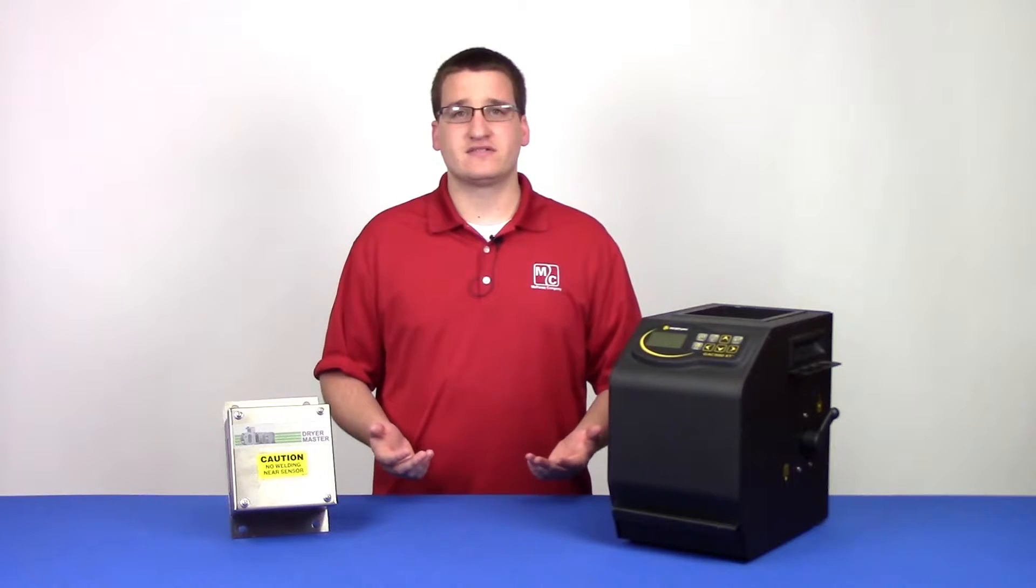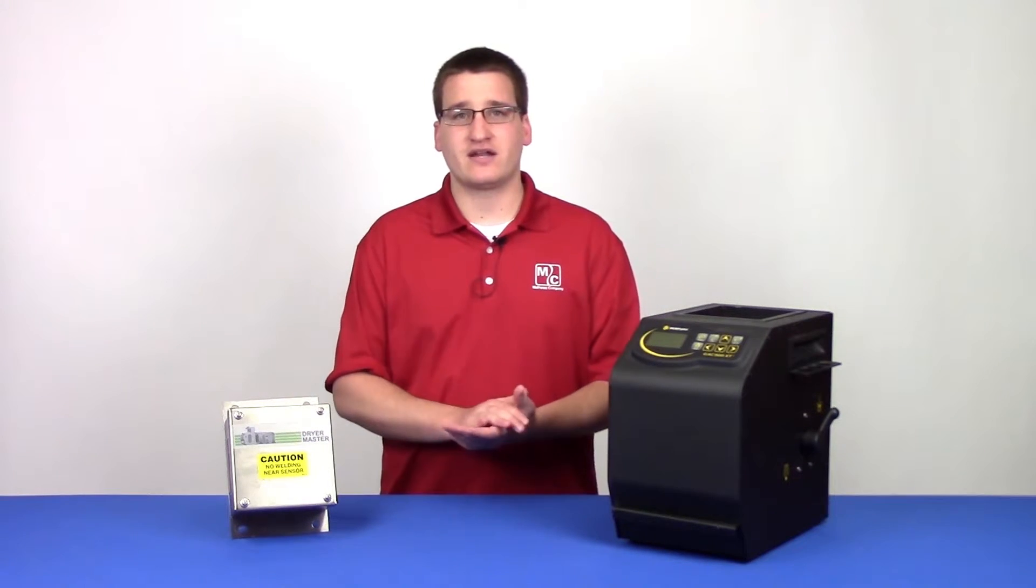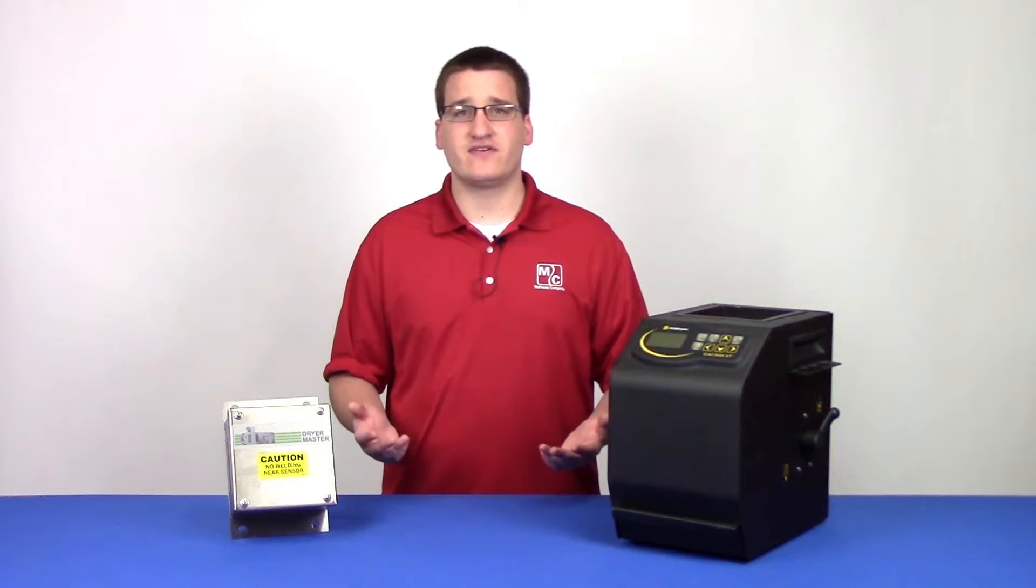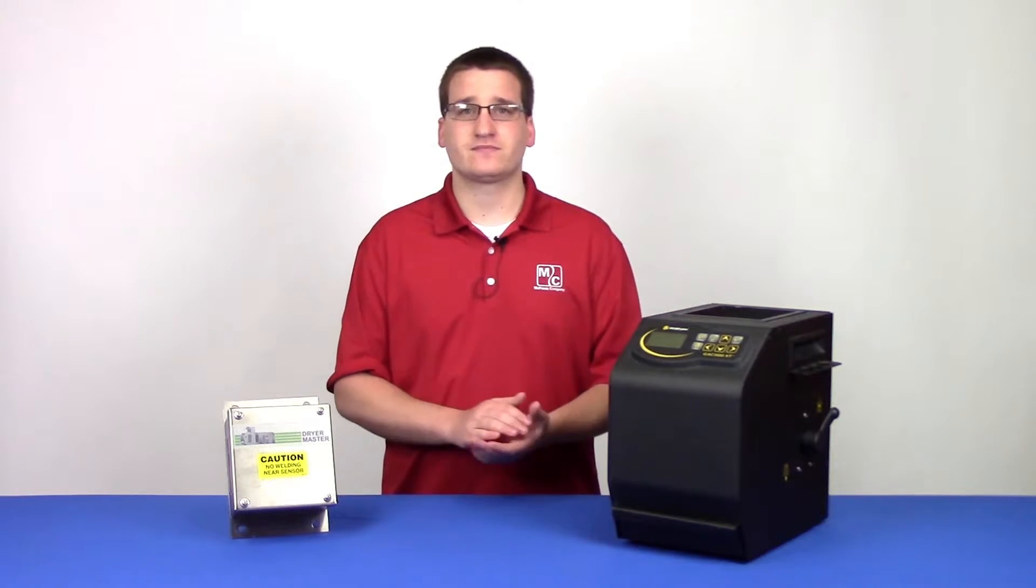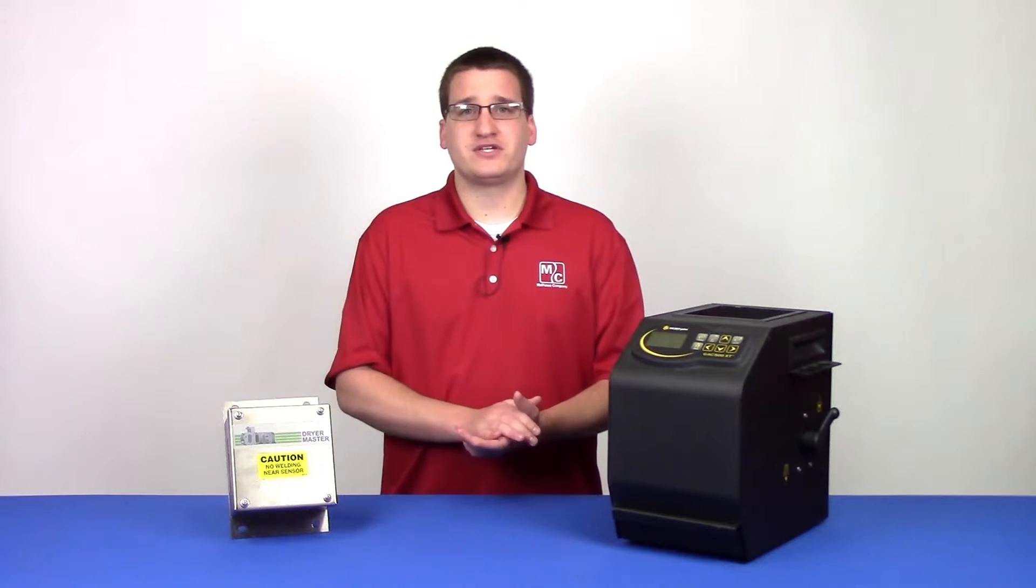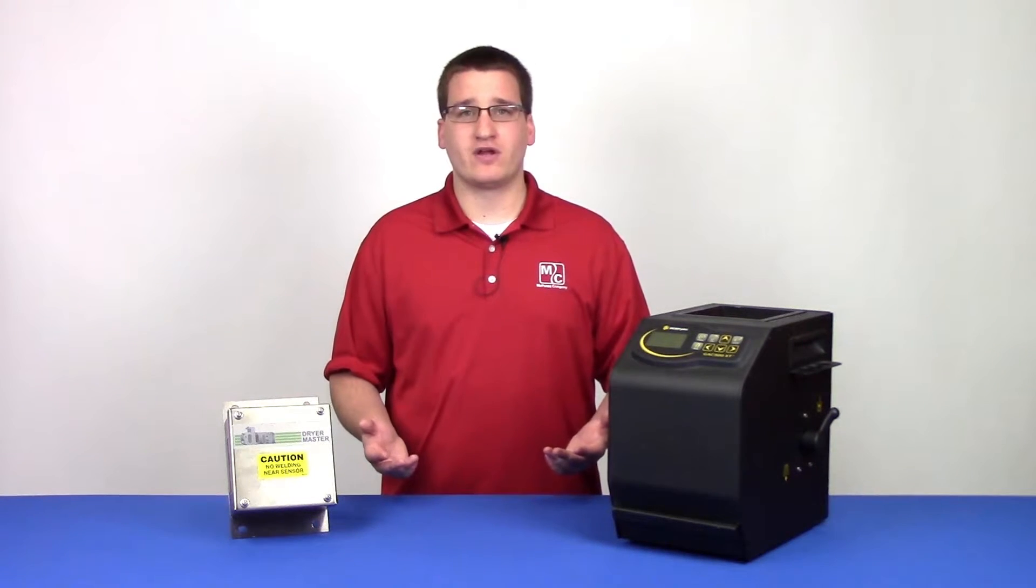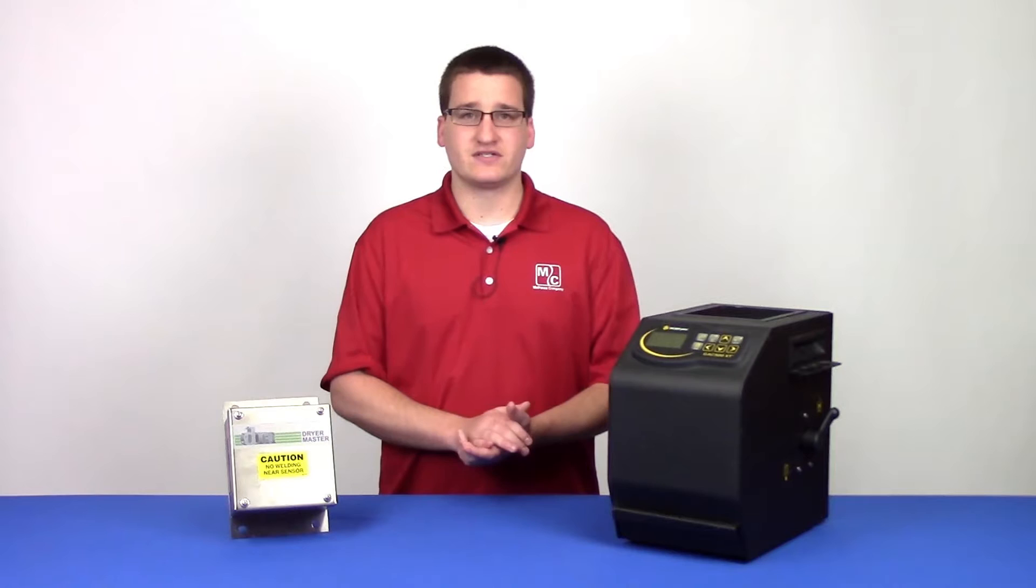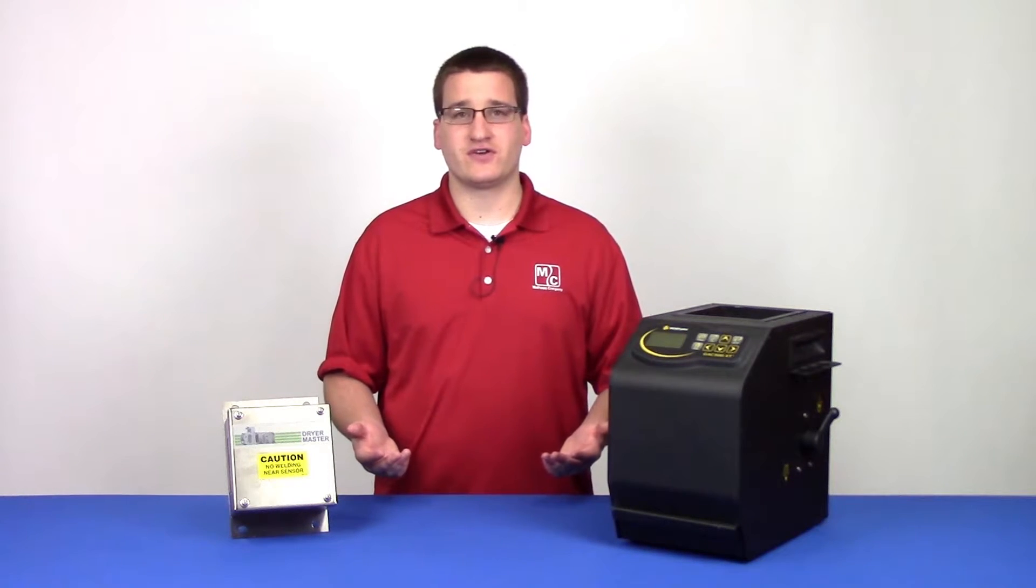Matthews recommends that the sensor is calibrated periodically throughout the season or any time there's a significant change to incoming grain. Also, it's important to note that sensor calibration must be done while the dryer is running under normal operating conditions and while the discharge grain is coming out near your desired set point.